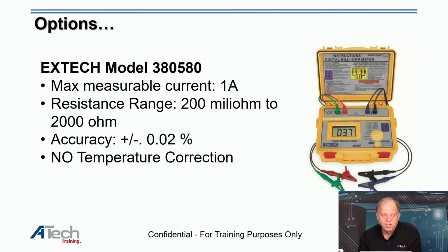If I got an EXTECH up here, again, the amperage current is 1. Notice it says 200 milliohms to 2,000 ohms. So the range on this one is not as good. The accuracy is 0.02. That's really good. No temperature correction on it again. And I think temperature correction is something that you probably want to have in the meter, as a suggestion.